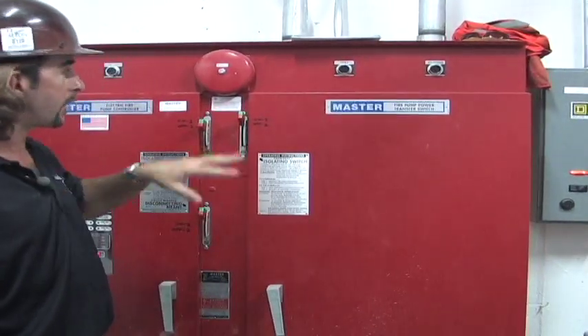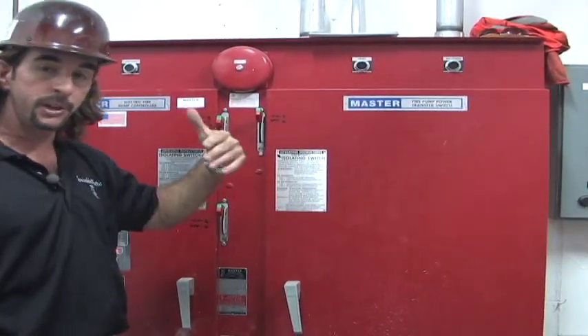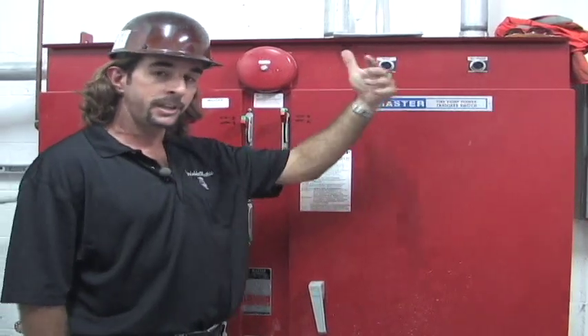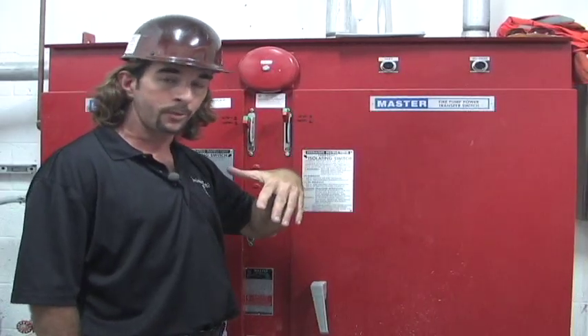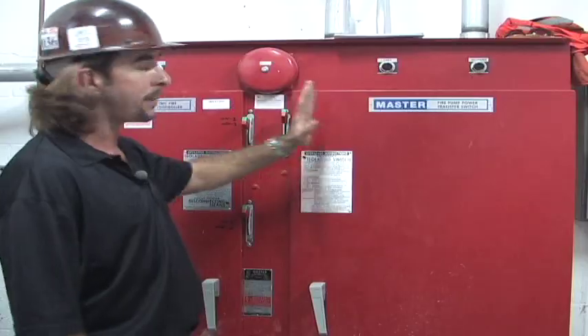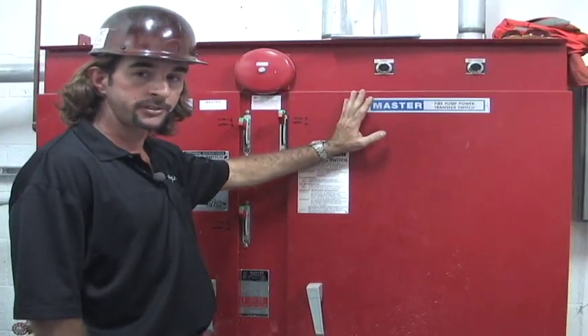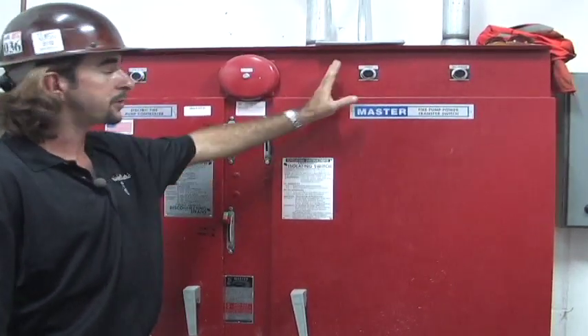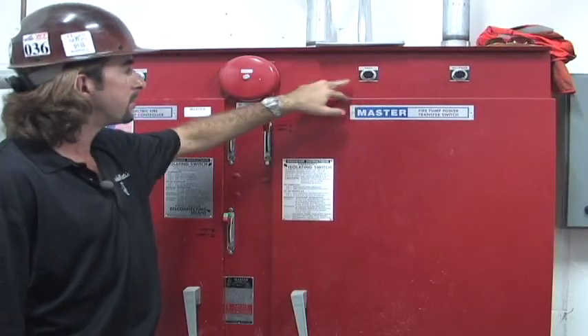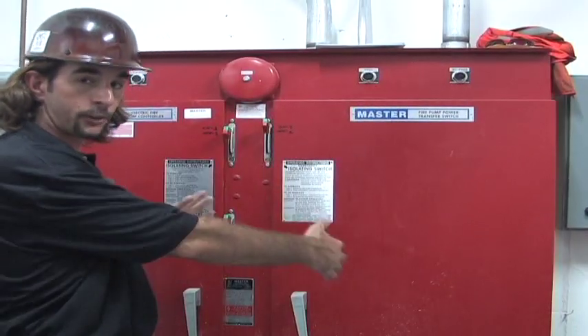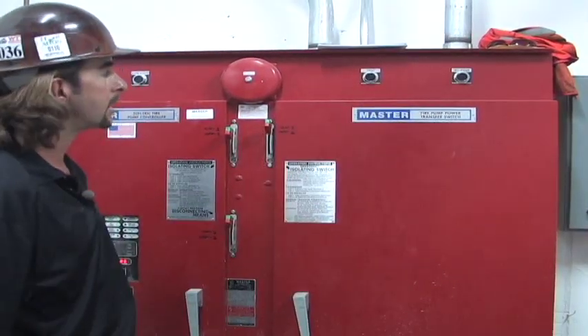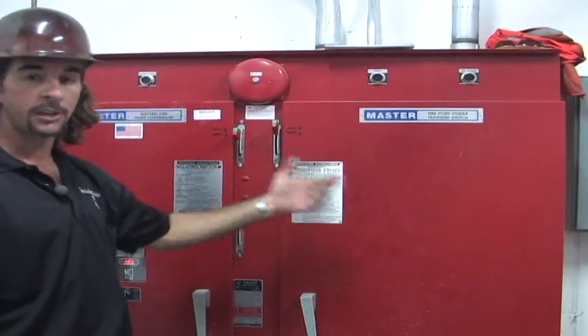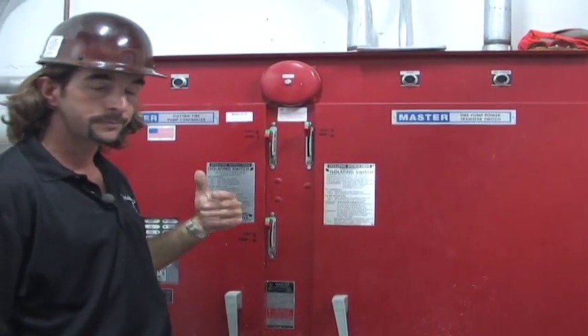As our fire pump is running, we're dumping water. If for some reason the fire department had killed the power to the building, the normal power, this would automatically switch over to the emergency. We're going to show that doing it in a manual state by going with the test button. It's going to transfer over into the emergency transfer switch, and then we're going to transfer it back to normal.